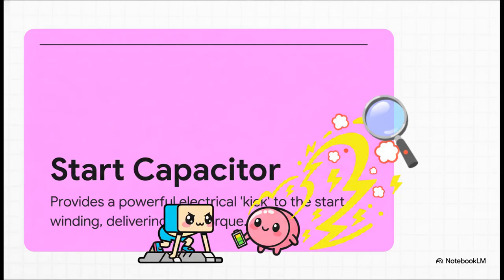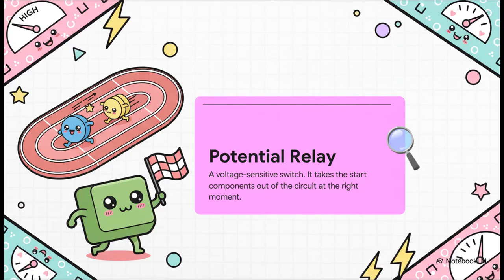So, to give our sprinter that explosive start out of the blocks, we have the start capacitor. It's like a battery that stores up a bunch of energy and then releases it all at once in a powerful kick, giving the start winding the juice it needs to create that initial turning force, what we call torque. And finally, we have the coach of the team, the potential relay. It's a voltage-sensitive switch, and its whole job is to watch the motor's performance and make that critical call to pull the sprinter, our start winding and capacitor, off the track at exactly the right time.